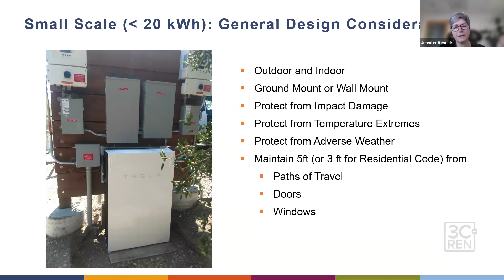The residential code then has some additional and specific requirements on battery sizes. The non-res requirements in Title 24, Part 9 gave you limits on battery capacity based on chemistry. The residential code is looking at this based on location - for example, depending on where it's located, it determines if you have to have type X gypsum, if you need interconnected smoke alarms, how close batteries can be near each other, and how many batteries you can have altogether.